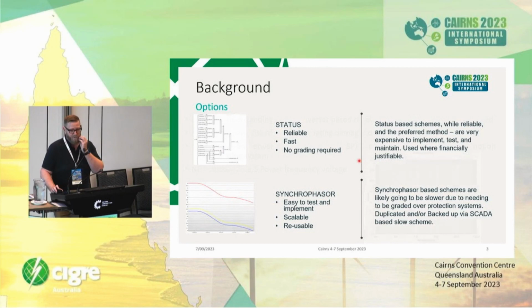So typically, the first response to something like this is to fall back to our business as usual of a status-based scheme of some kind. So what can we wire to a protection relay? What can we send via signalling to wherever needs it to be able to respond? But historically, and most people probably experience this, while they're reliable and fast, they can be very expensive to implement, test, and maintain. And when it comes to modifying them, and the way the system's going at the moment, you tee off a feeder somewhere and then all of a sudden you're having to do all this rework, visit all these substations that weren't supposed to be part of the initial project scope, et cetera, et cetera. So the costs can blow out, and we saw that.